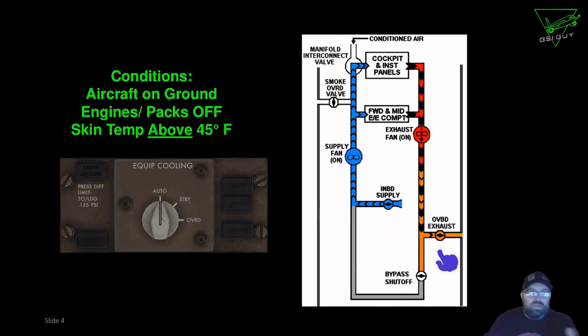We still have the supply fan running and the exhaust fan running. Our interconnect valve here is not switched to conditioned air yet. So we literally have a supply fan shoving the air in, and an exhaust fan pulling the air through and then dumping it over the side. So far we're still in normal configuration, normal settings, in the auto mode.